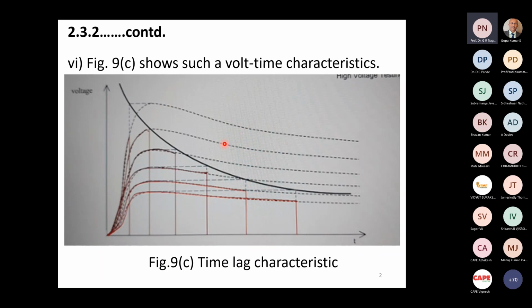I cannot assure that. If the ionization is there, we have seen from the earlier experiments by Allen and Mikropoulos that again the breakdown is probabilistic. And then the velocity of propagation reduces because we're reducing voltage in the impulse field. There it was a uniform field, a constant field - here it's a reducing field, so the velocity of propagation reduces. So you'll see that because of this additional behavior of the voltage time characteristic, there's an additional factor which declares that an assured 10 microsecond differential is simply impossible.